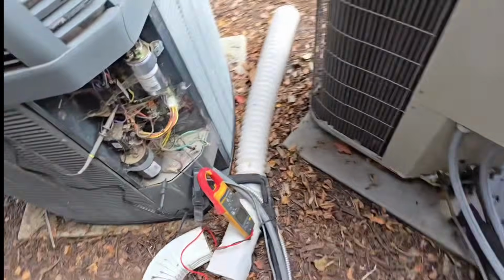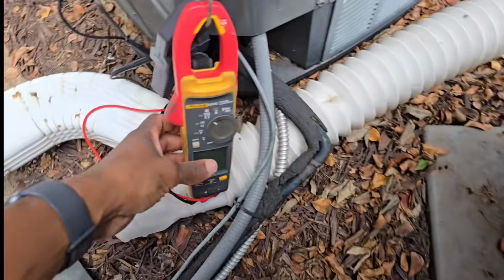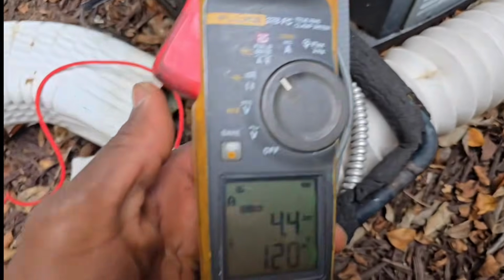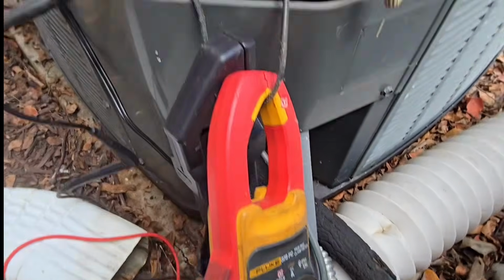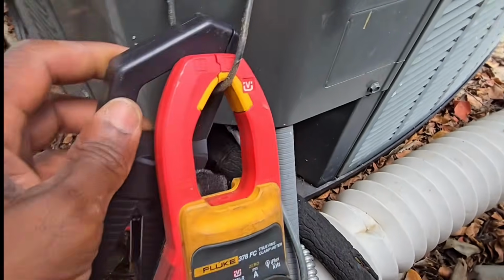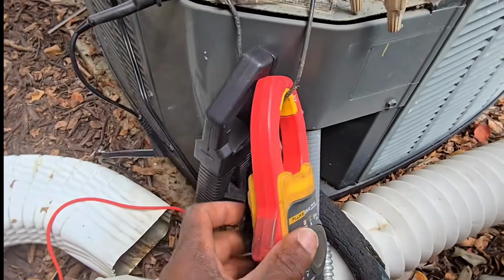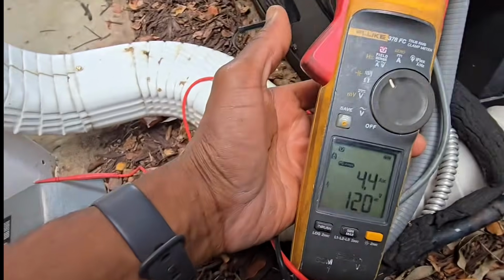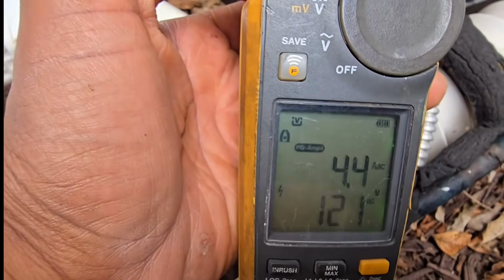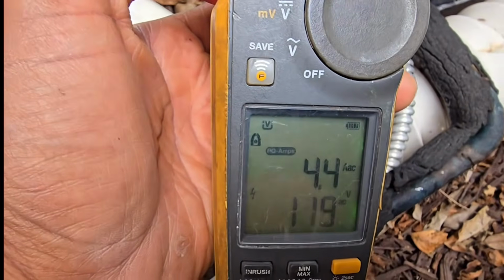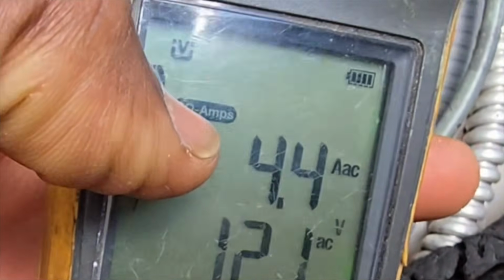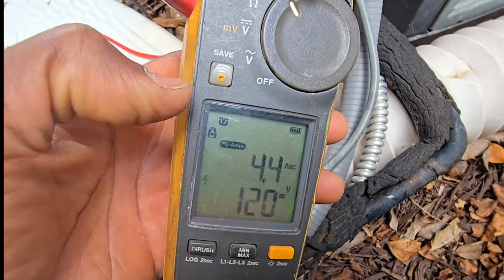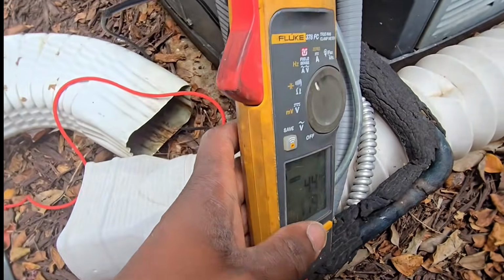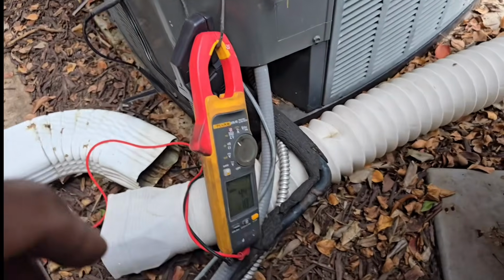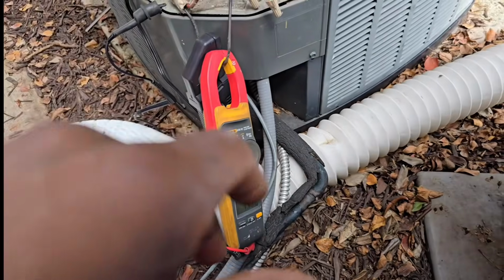And you can see here, I've got my Fluke 387 FC, and I'm checking the same current. Got the clamp here for the oscilloscope, and here's the clamp for my Fluke. You can see we've got a power quality fault there. That little indicator is showing power quality on your amps is low, so there's going to be a lot of harmonic distortion in the line.